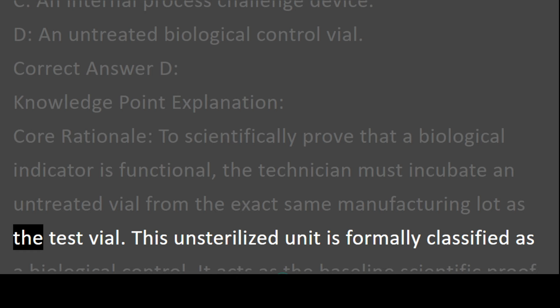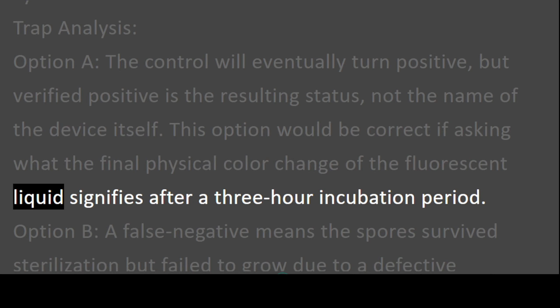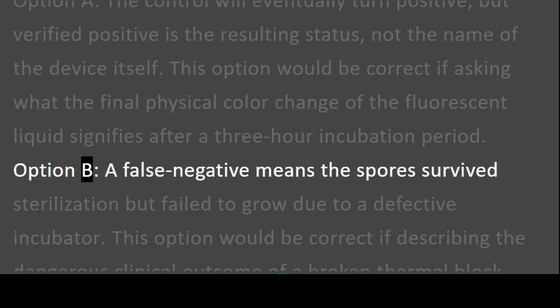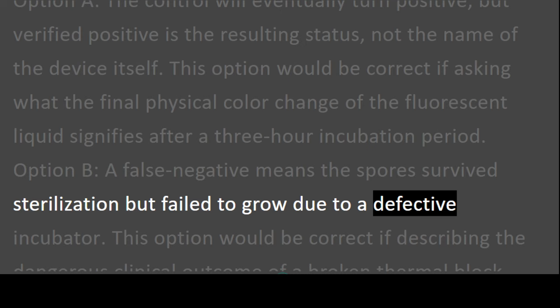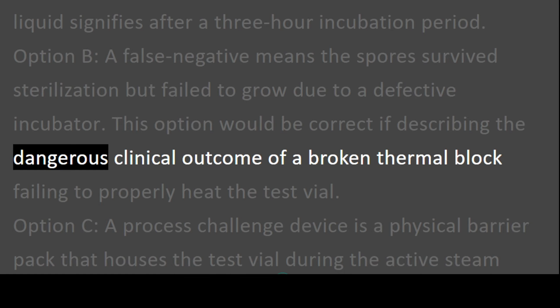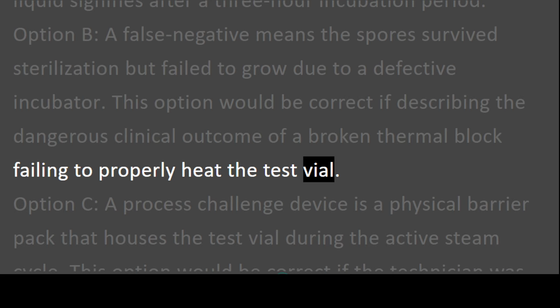Trap analysis. Option A. The control will eventually turn positive, but verified positive is the resulting status, not the name of the device itself. This option would be correct if asking what the final physical color change of the fluorescent liquid signifies after a 3-hour incubation period. Option B. A false negative means the spores survived sterilization but failed to grow due to a defective incubator. This option would be correct if describing the dangerous clinical outcome of a broken thermal block failing to properly heat the test vial.